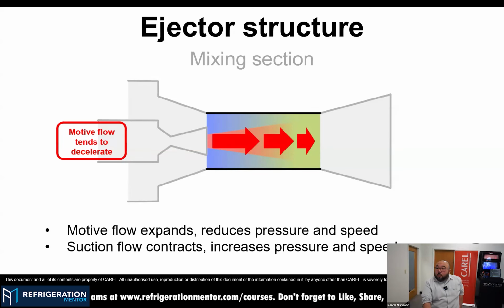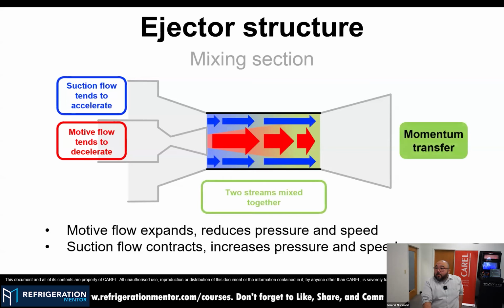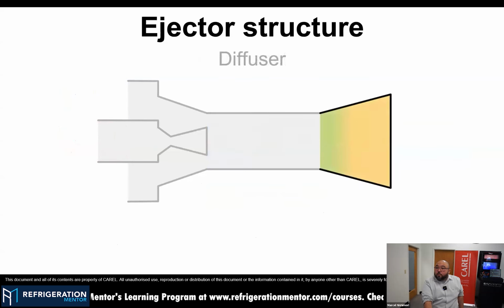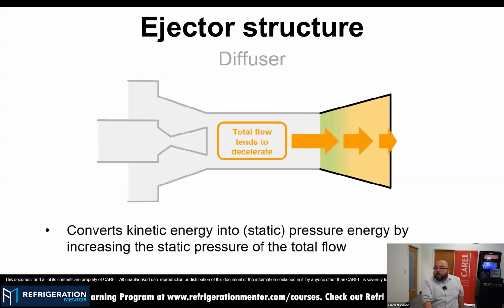Yeah, that's correct. So we are making the mixing here, and we have what we call momentum transfer. I'm using the kinetic energy from a refrigerant at higher speed to drag and compress the other refrigerant. So at the end of the day, the total amount of energy is the same, but we are basically transferring the energy coming from the gas cooler refrigerant to the MT suction line to increase its pressure. So no magic here. It is just transferring the energy between the two different fluid conditions. And as a consequence, we have here the total flow that goes to the liquid receiver.